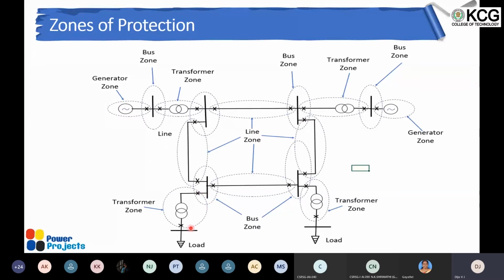So what is expected is that if there is a fault on the line somewhere here, only this part trips. This breaker should operate and also this breaker should operate. So this fault will be cleared by the opening of these two breakers. It's all very basic, but I thought it would be better to give an idea about it. Now we'll go to the different types of protection.